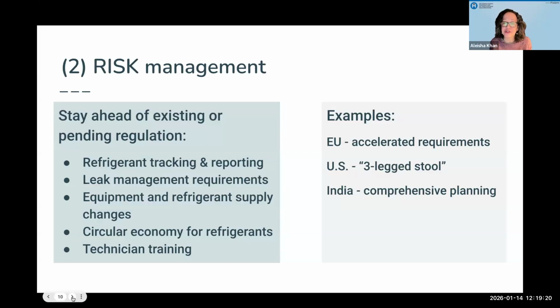The second reason to talk about refrigerants is risk, specifically managing risk in the face of existing or pending refrigerant regulation. Getting in front of this can be extremely helpful from a capital expenditure planning perspective. You might have facilities in different countries with different regulations, and knowing the timetables for new requirements and planning ahead before you face higher prices and shortages can be very strategic. At a high level, regulation generally has some combination of refrigerant tracking and reporting requirements, leak management, and a shift in the supply of high GWP equipment and refrigerant.